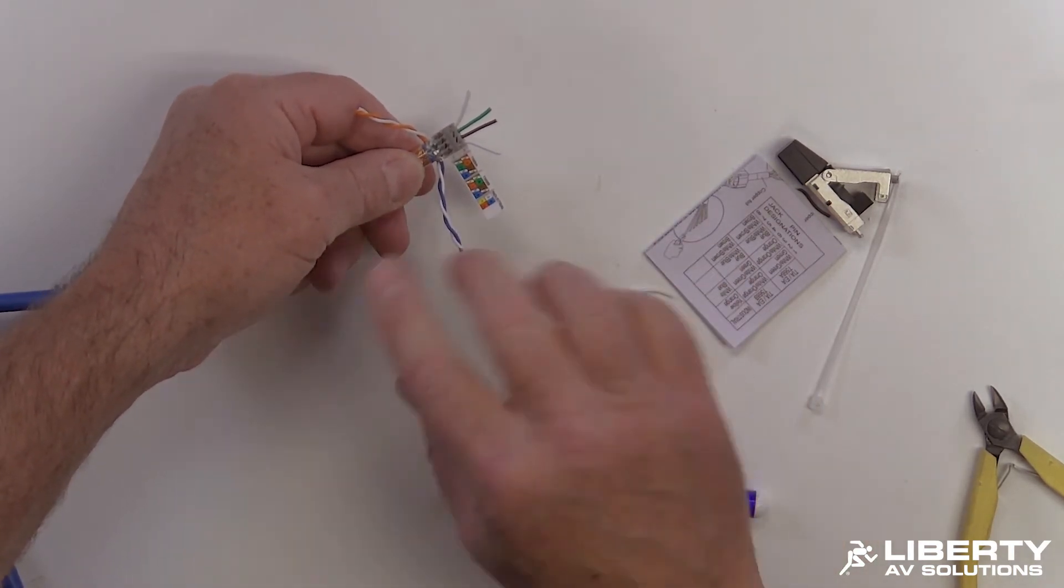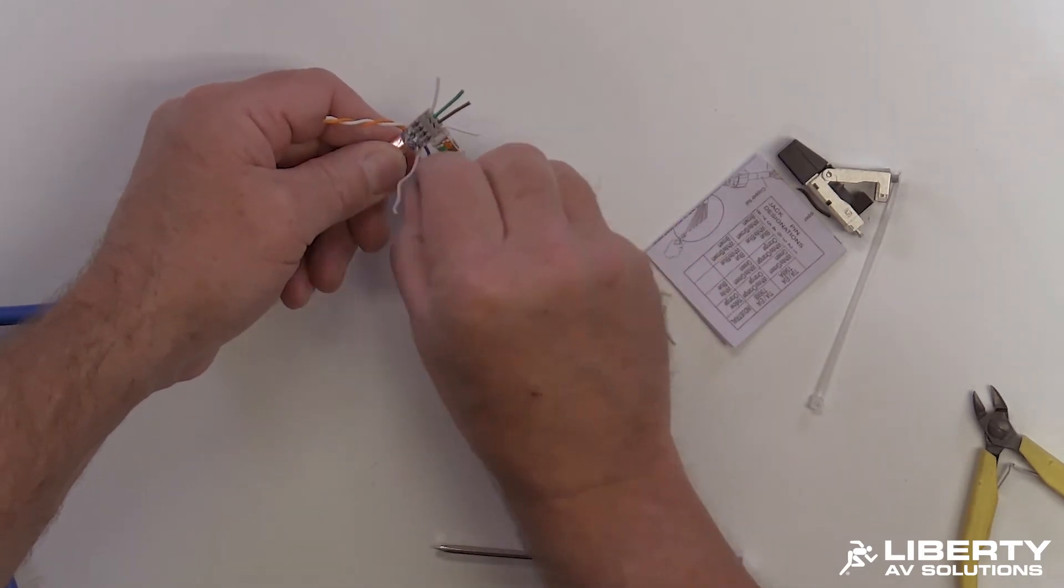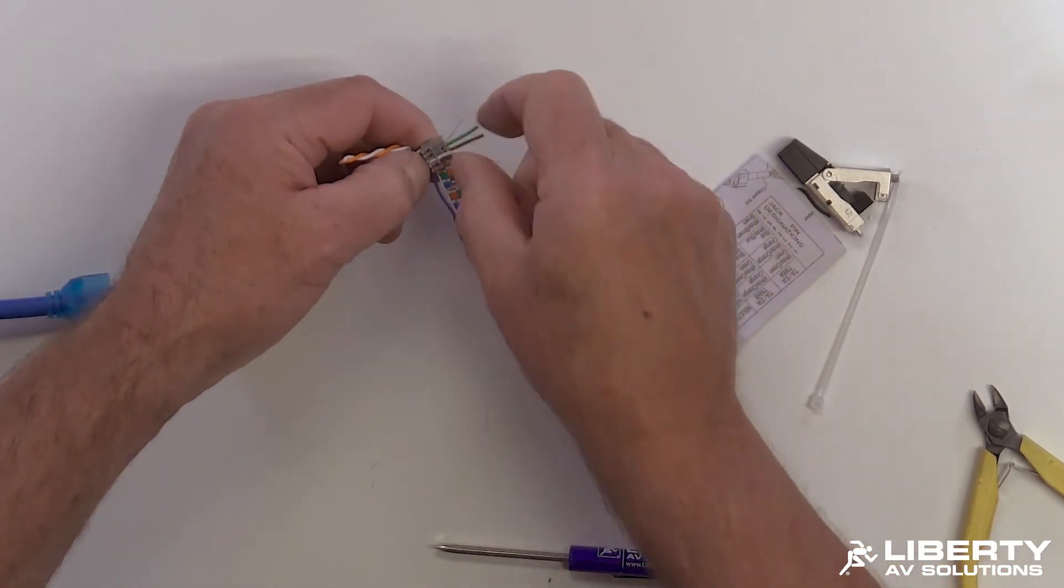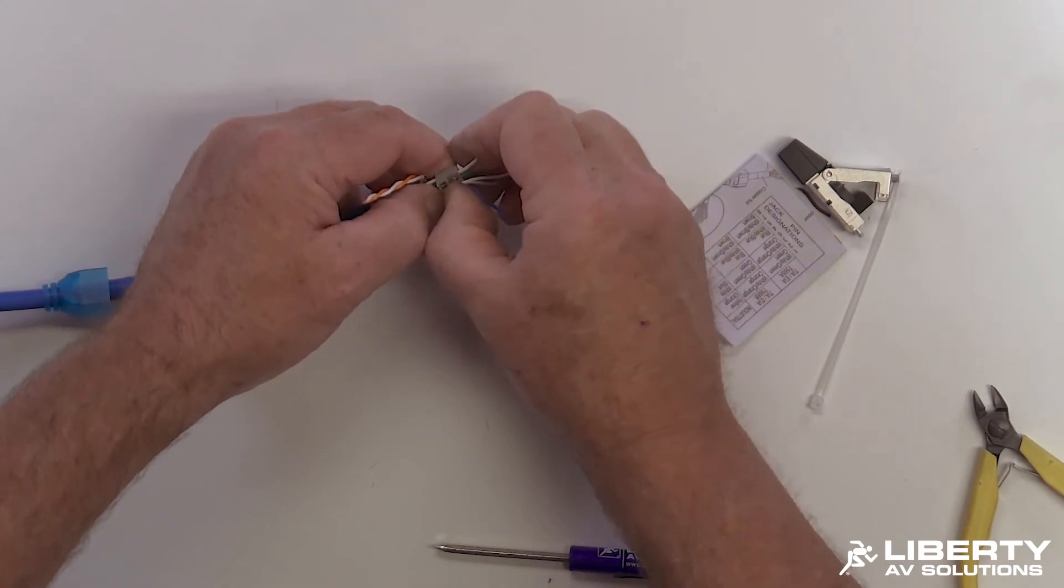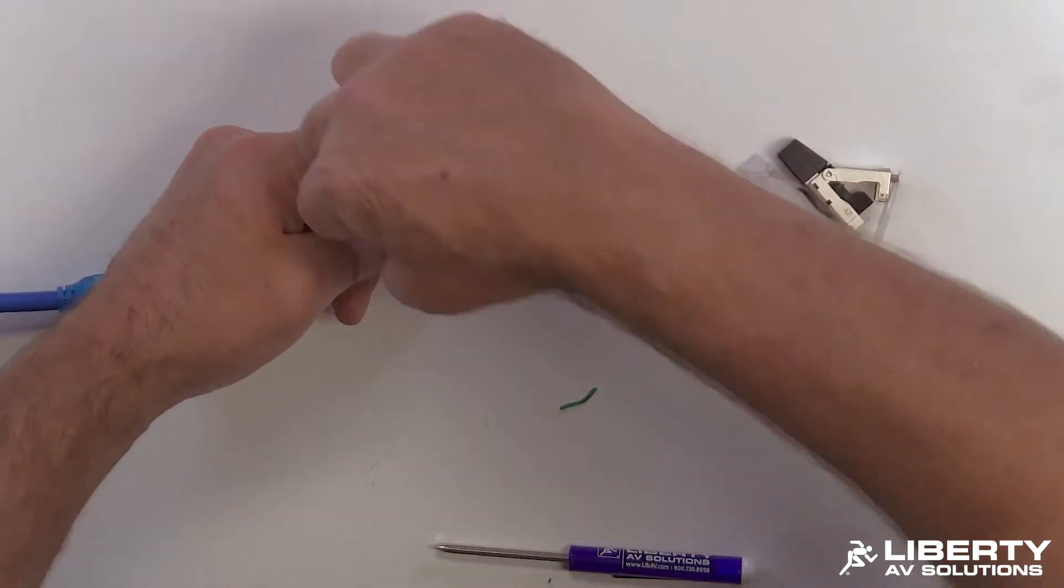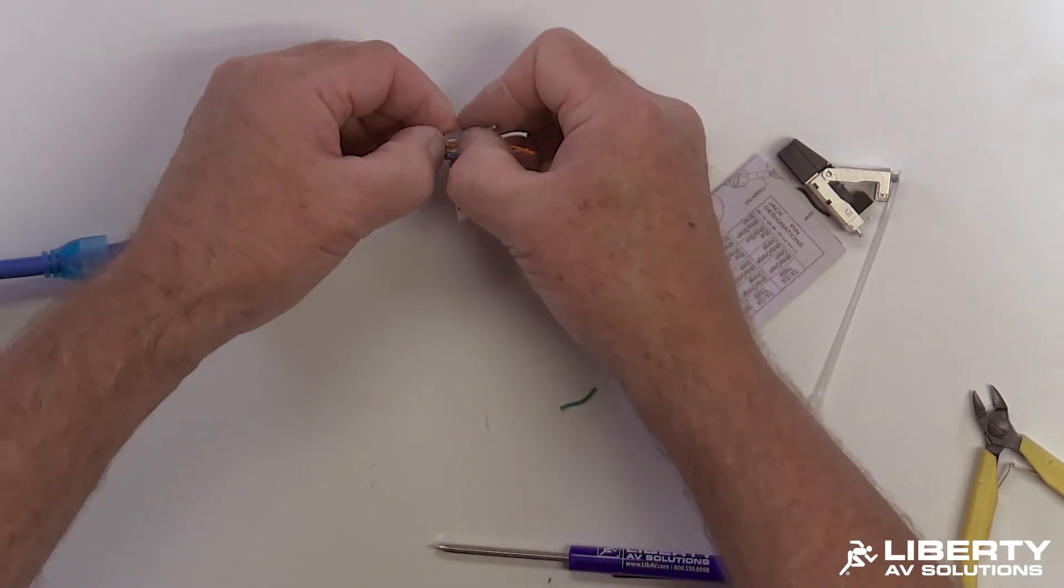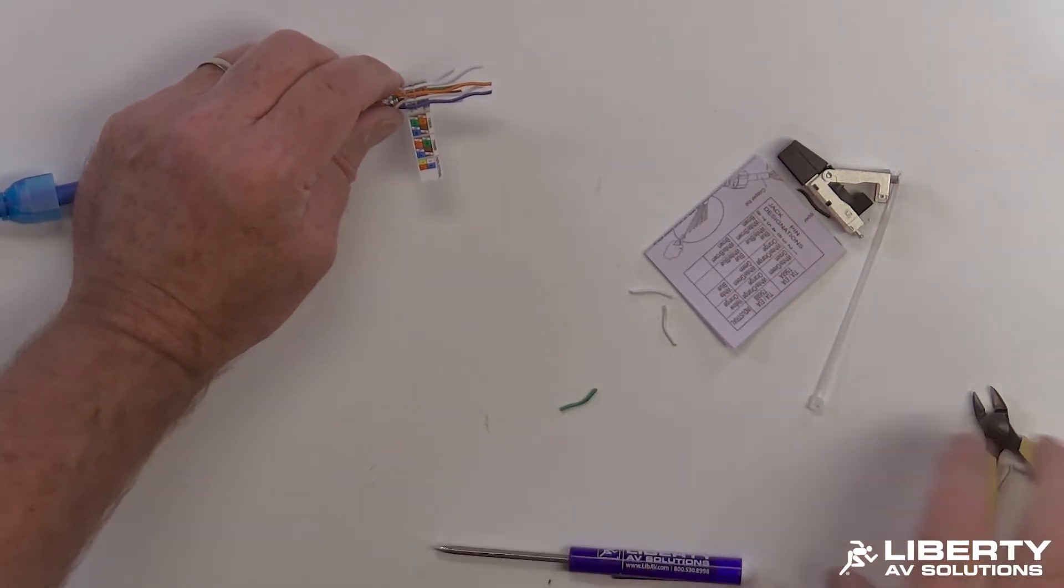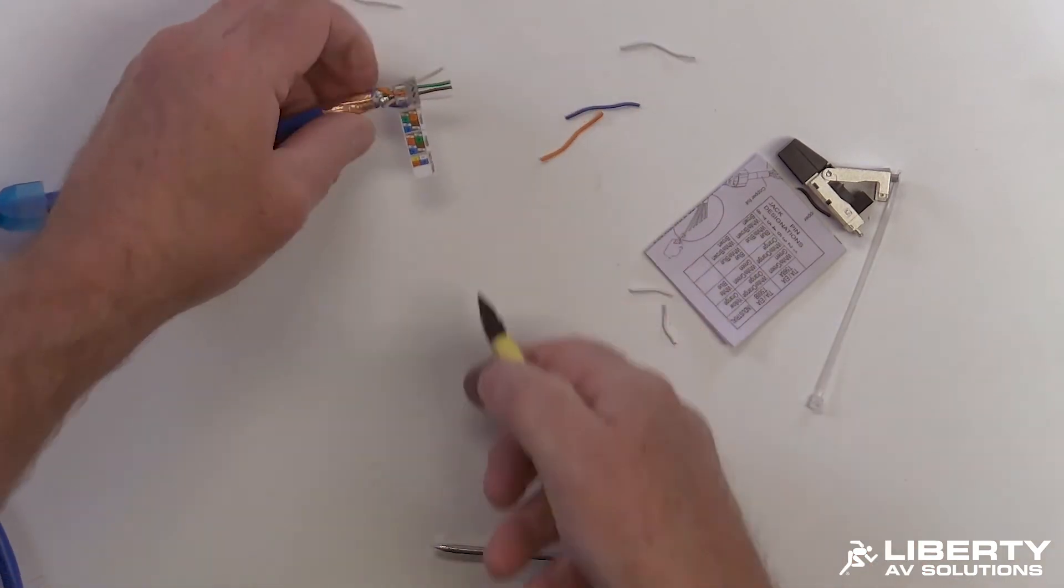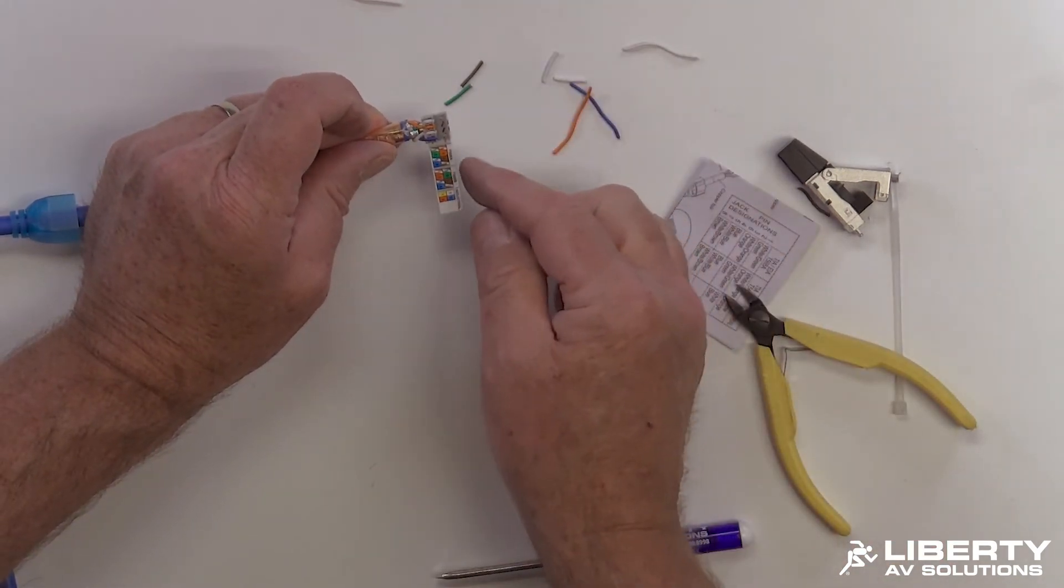Now you can pull your other wires up and around. Depending on which side of the cable you're terminating, one side will always be completely backwards to the other. So this is actually the difficult side where the other conductors are underneath. You can untwist these. Again you can use the tweaker. You can do it by hand, either one. Put these also in the correct color code. These actually slide into these grooves and it locks down. You can feel it kind of click when it locks in place. You can use an insert tool to do it too. You can go ahead and use basically a 110 insert tool to put it in there. But these are actually pretty easy, so you don't have to go that far. So once this load bar is fully loaded, all the conductors are in there, I can go ahead and trim these now. So I can go ahead and trim off all these wires. Flush to the plastic. So the top row is flush to the top and the bottom row is flush to the bottom. Verify the color code. You can do that before you trim or after, but just verify that color code.